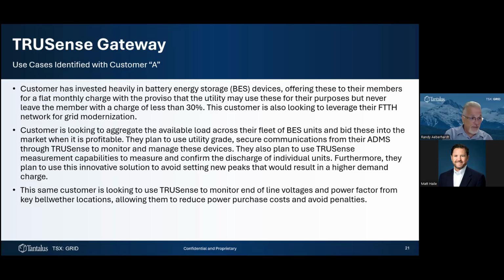They get immediate feedback from end of line devices into their SCADA system, so they know whether there's still room to lower voltage further, or if they've gone too far and need to bump it up. This allows them to really optimize their power purchase costs. Similarly with managing power factor, because if they've got bad power factor, they're using more energy to compensate. So really the two things go hand in hand - voltage levels and power factor.